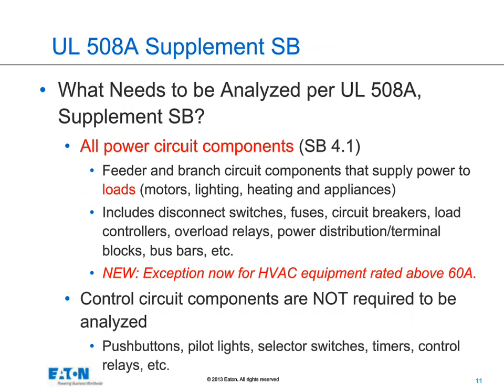Looking at UL508A Supplement SB in more detail: a common question is what components affect the SCCR of the assembly, and the answer is only power circuit components — those that supply loads. Loads to consider would be motors, lighting, heating, appliance, and often receptacles. So disconnect switches, fuses, breakers, and controllers that supply those loads would affect the SCCR. A new exception added in December allows that HVAC equipment rated above 60 amps does not affect the SCCR, and an enclosure air conditioner in an industrial control panel does not affect it either. Control circuit components such as push buttons, pilot lights, and selector switches also do not affect the SCCR.